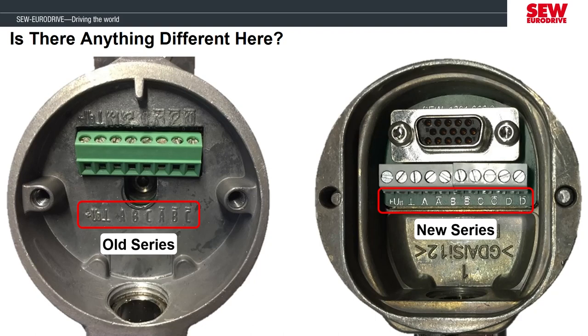You'll also see an addition of the D channel, but that is only used on absolute encoders for the data channel. These new style connection covers can be used on several different encoder types, which is why it's included on the terminal strip even if it's not used. This difference could easily be missed, presenting a problem when replacing an old motor with a new one — if you took a picture of the old wiring, you may not notice that the channel labels have moved positions.